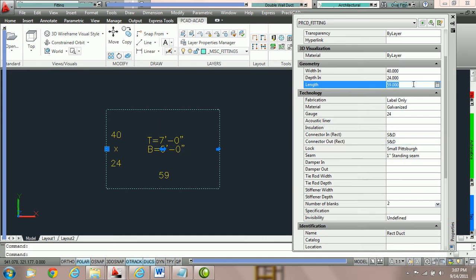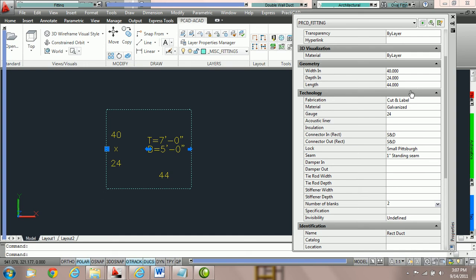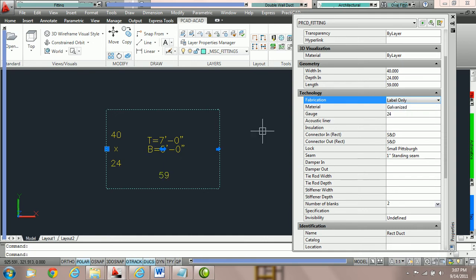For example, if we take the length and switch it from 59 inches to 44 inches and hit Enter, PractiCAD will say you are not following the default stock length and therefore switch the fabrication level to cut and label so it sends it to the plasma. If we switch it back to label only, PractiCAD will re-edit the fitting and make sure that based on the connections it meets the default stock length. You can choose between cut and label and label only — this shift will most of the time be automatic, but you can choose to change the fabrication level at any time.